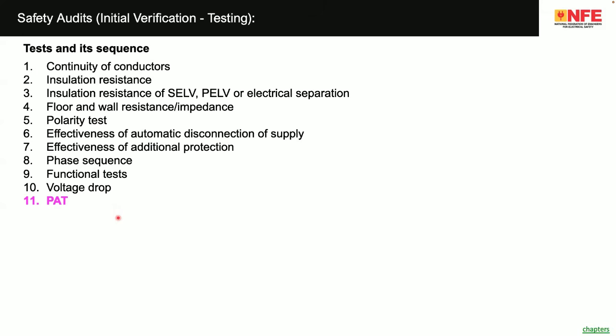And in hospitals, especially in OTs and ICUs, this is a real hazard. Fire from air conditioners has been reported on multiple occasions. If you do a PAT test once in a while, maybe once in 6 months, it's a small instrument, maybe costing 30,000-40,000 rupees. Hospitals can buy it, keep it with the technician, and he can make the test whenever the area is free. You can very easily find out the fault of the equipment.